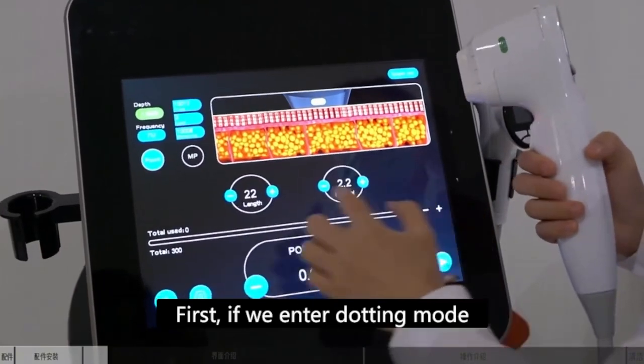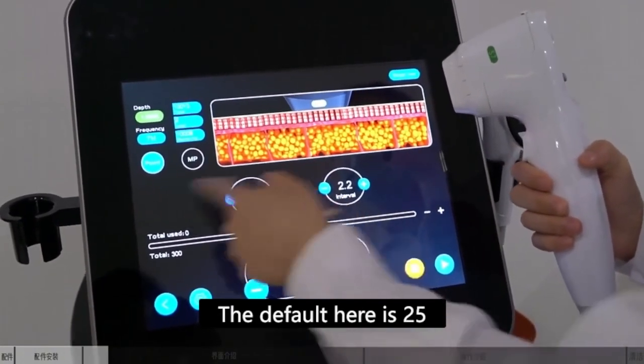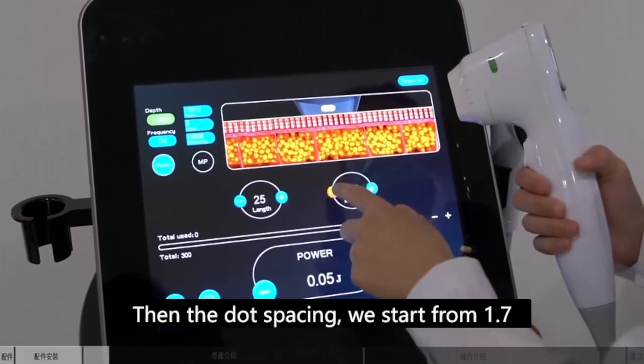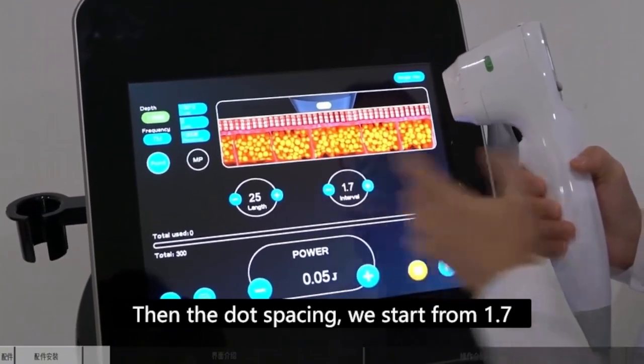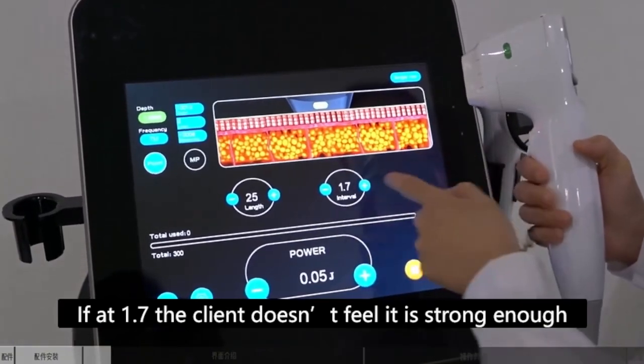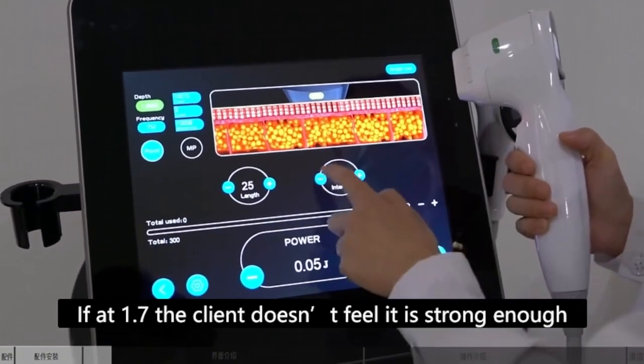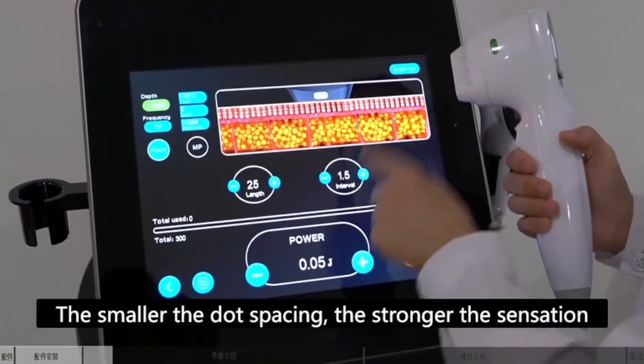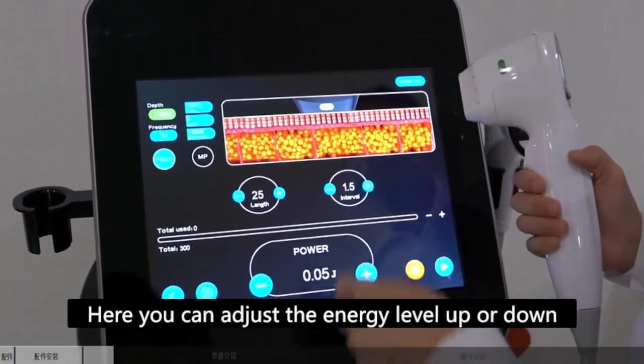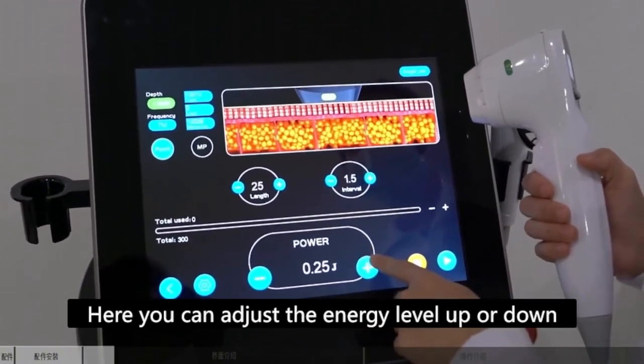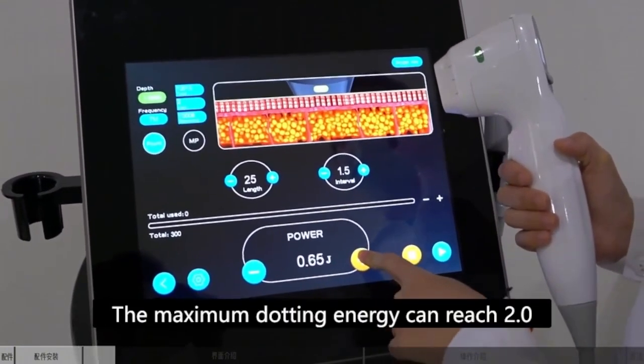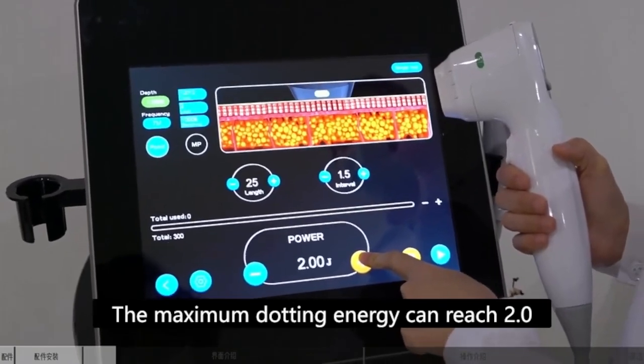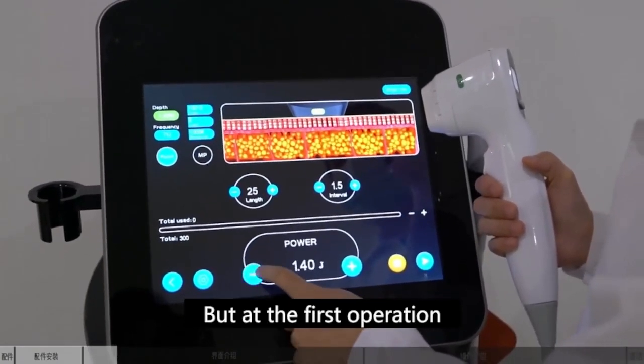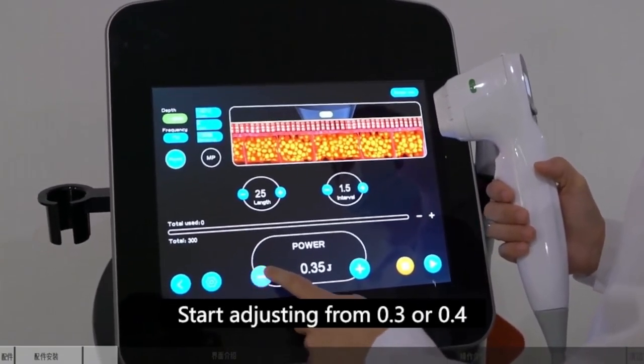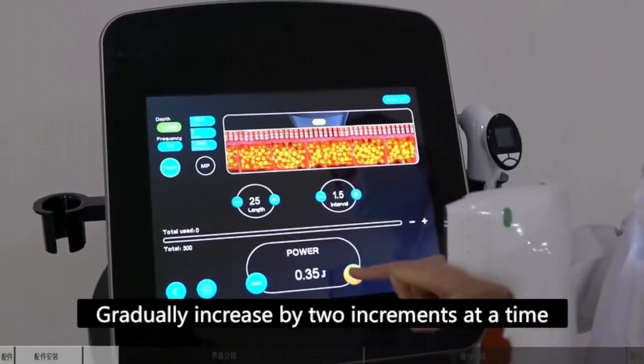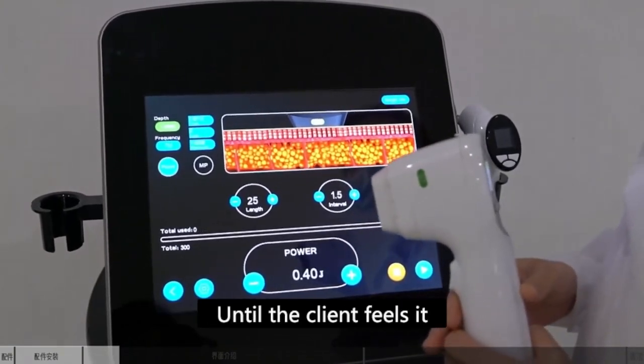First, if we enter dotting mode, the default here is 25. Then the dot spacing, we start from 1.7. If at 1.7 the client doesn't feel it is strong enough, we gradually reduce it appropriately. The smaller the dot spacing, the stronger the sensation. Here you can adjust the energy level up or down. The maximum dotting energy can reach 2.0. But at the first operation, start adjusting from 0.3 or 0.4. Gradually increase by 2 increments at a time, until the client feels it.